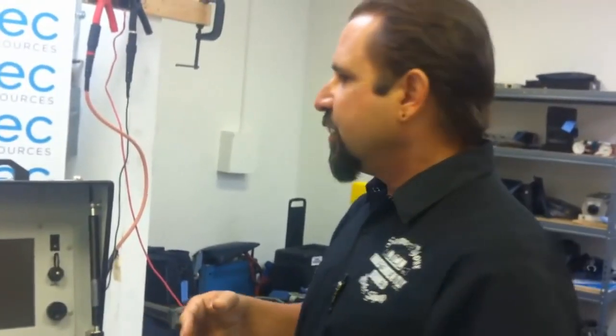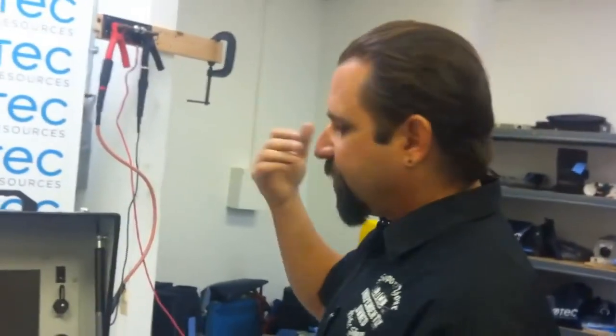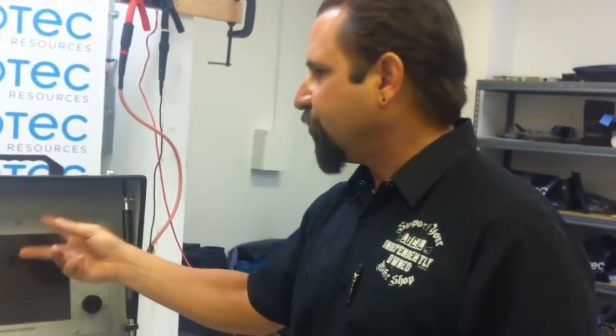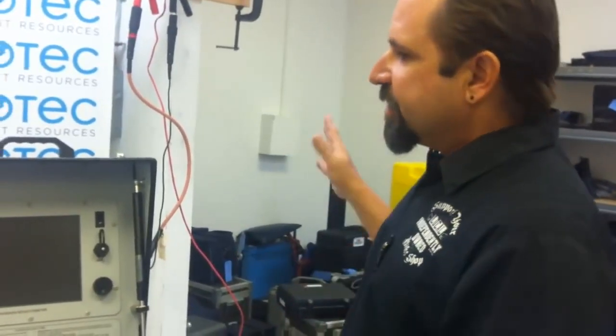So I can also test out the radar, make sure that we're getting proper radar patterns, that we have the open gap, do the arc reflection test, make sure that it sparks over, the radar triggers, gives us the updated high voltage picture. So this is the way that when the unit comes back in from a rental, we're going to go through and just validate that everything within the high voltage system, within the radar coupling, and within the radar unit are all operating properly before going out to our next client.